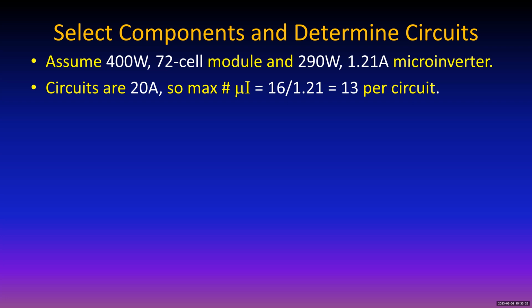So how many microinverters can we have in a 20 amp circuit? Well, the maximum output current is 1.21. The maximum continuous current for a 20 amp circuit is 16. So you can have 13 per circuit, pretty straightforward. So for a whole host of different modules, if you use this particular microinverter, you can have 13 per circuit, and that's it. And then you start another circuit.